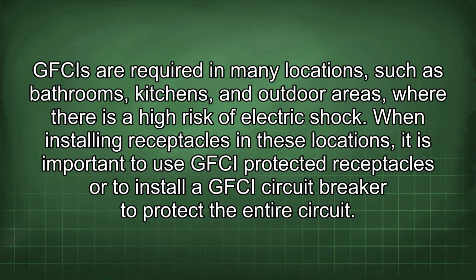GFCIs are required in many locations, such as bathrooms, kitchens, and outdoor areas, where there is a high risk of electric shock. When installing receptacles in these locations, it is important to use GFCI-protected receptacles or to install a GFCI circuit breaker to protect the entire circuit.